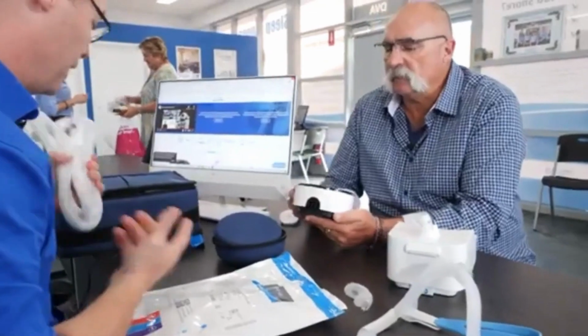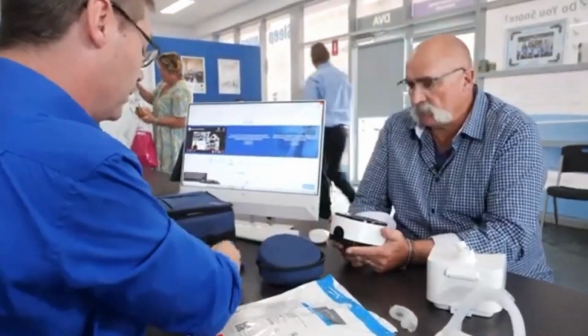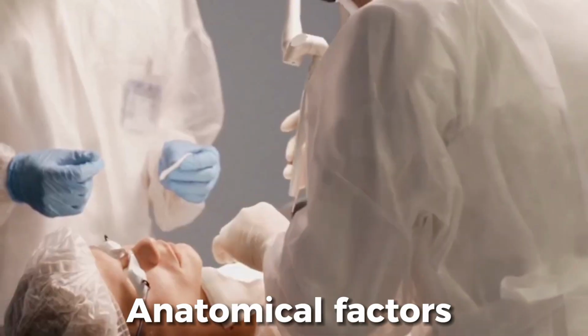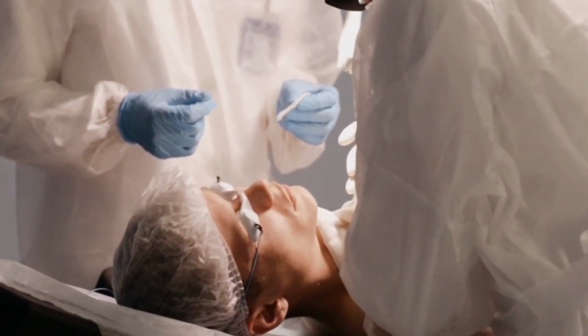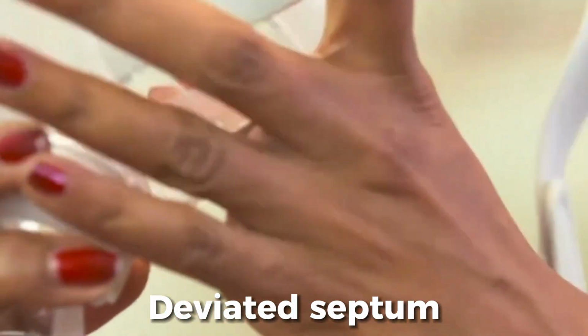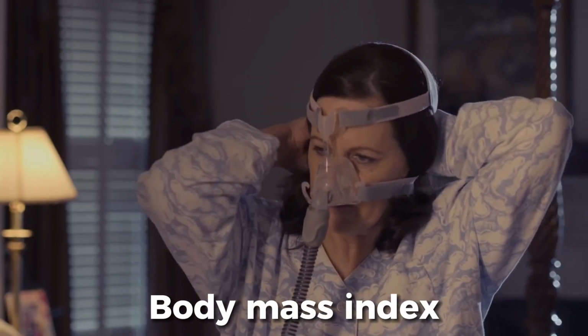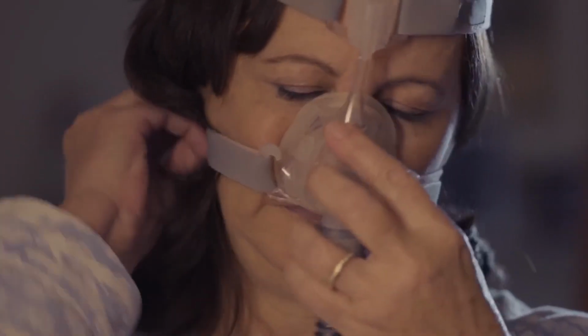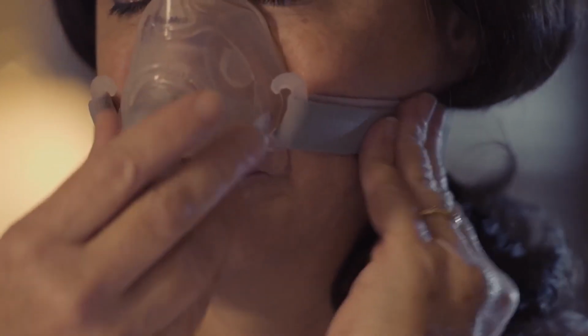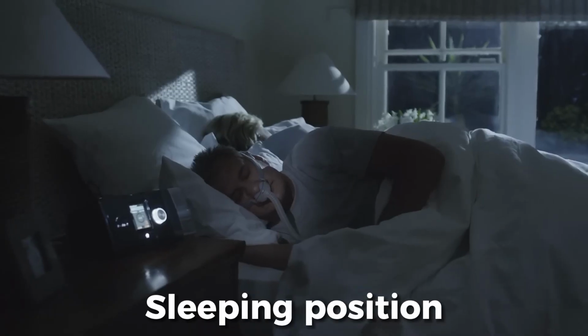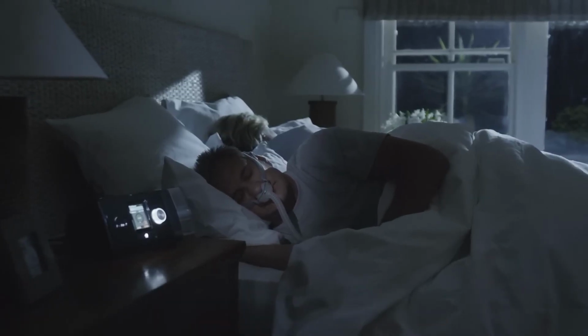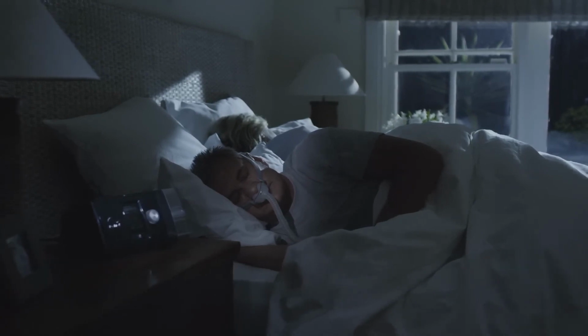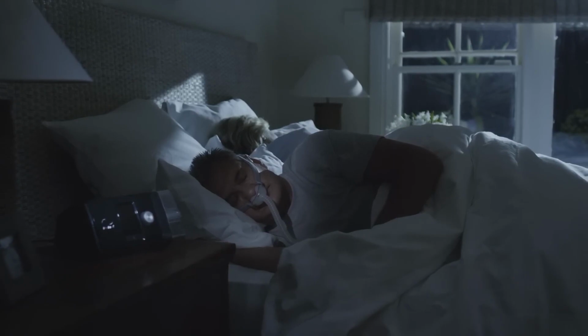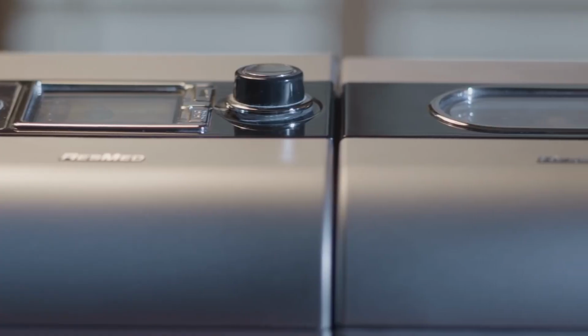Some factors that affect the pressure settings for the CPAP machine include anatomical factors such as people with smaller lower jaws, large tongues or tonsils, or a neck circumference over 17 inches. A deviated septum limits airflow through the nose, so typically a higher pressure may be required. The body mass index, because overweight people are more likely to have extra throat tissue, restricting airflow to the lungs. And your sleep position, as sleeping on your back is generally believed to be the worst position for sleep apnea, as the downward pull of gravity puts even more pressure on the airway. Back sleepers will typically require higher pressure settings.